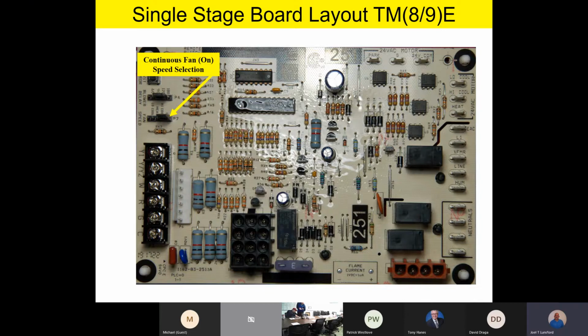So the selections are G, which is going to be a very, very low speed if it's just a G-only call. You can also run the fan at high cool speed or low cool speed, or you can run it at the heating speed. So that's kind of neat. It gives you 4 selections of how fast you would like the fan to run in the event you went to the thermostat sub-base assembly and changed the fan from auto to on. So it gives you some nice options for continuous filtration, especially if the homeowner has installed some IAQ devices, for instance, a really nice air filtration system. Oftentimes they like to keep the fan running all the time to keep that air moving through the filter. So that gives you some really nice options other than just off or on. We actually give you 4 speed selections for continuous fan.